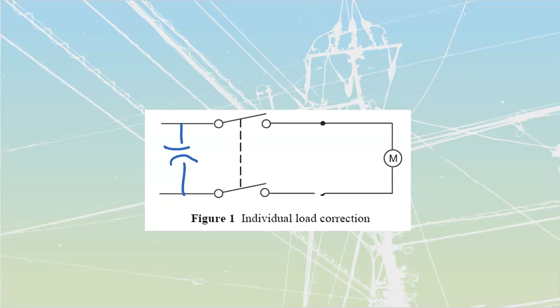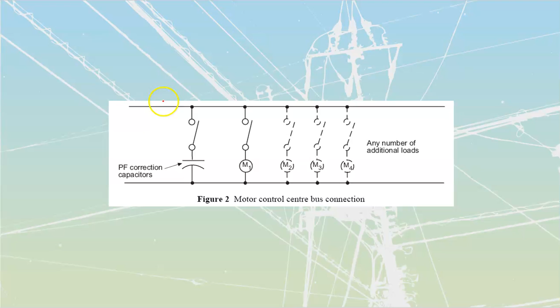Feeder correction is where I have multiple smaller motors - we saw that in the hydro handout as well - but I use one power factor correction capacitor to correct a whole pile of motors. Sometimes it's done with multiple smaller ones, so that as each individual one comes on, I correct that feeder. Then I don't need these things dropped all over the plant by my motors or anything; I just have them all as a central grouped hub inside my electrical room.